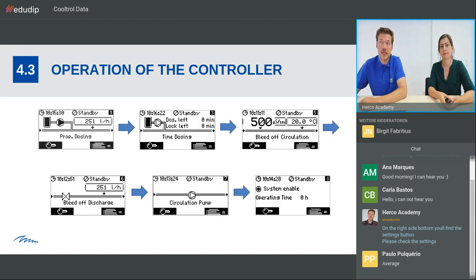All right, so we have different operation displays. You always see in the middle the actual operation or the information stage you're at. For this one, it would be proportional dosing. And then you see if you're actually operating the system. This one is standby, actually, the time, and also the actual flow where you dose to. Then for time dosing, we also have the state, and in the middle you have the dosing time left and the lock left. You remember the lock is for keeping the chemicals inside, and then also how long we are dosing, how long we are locking. And that's basically all the information you get there.